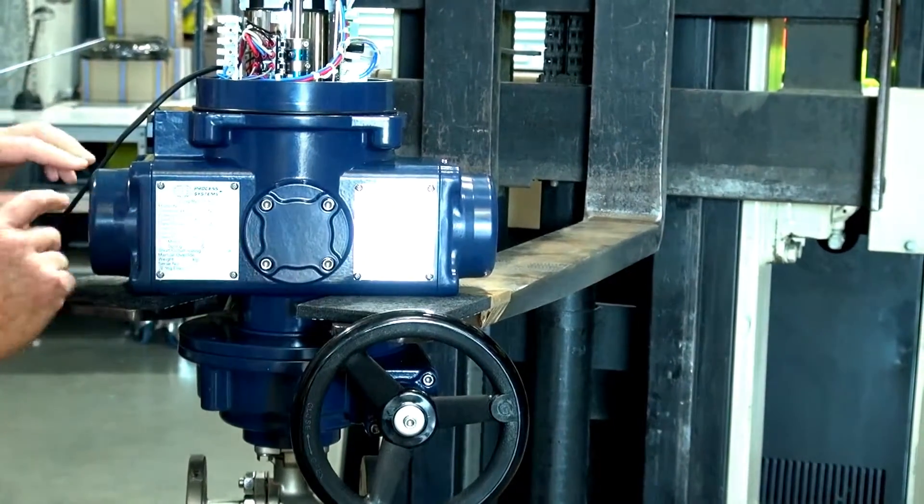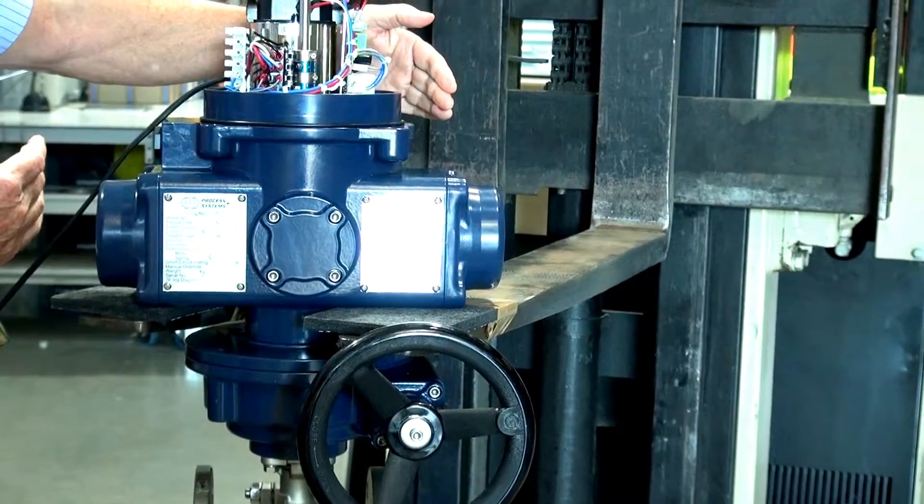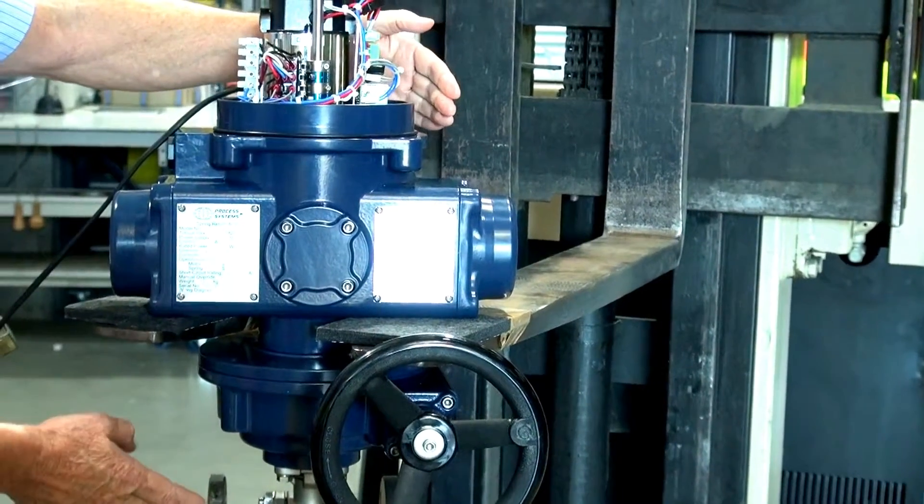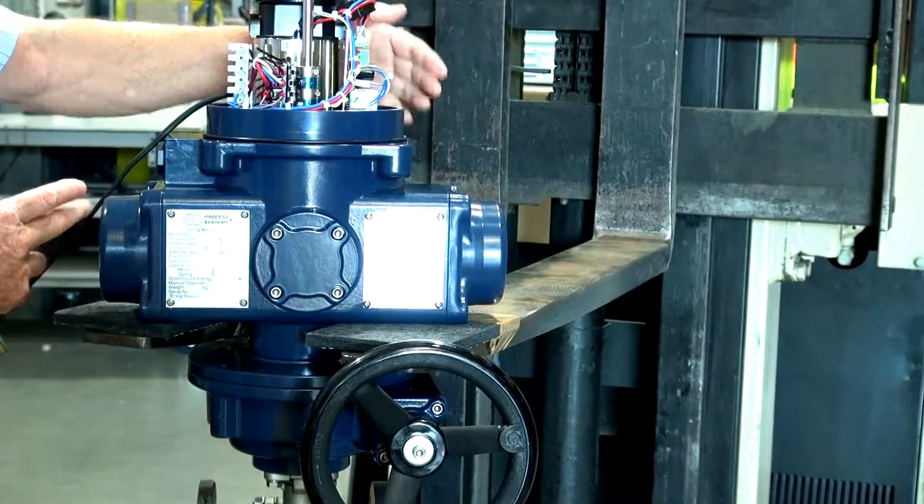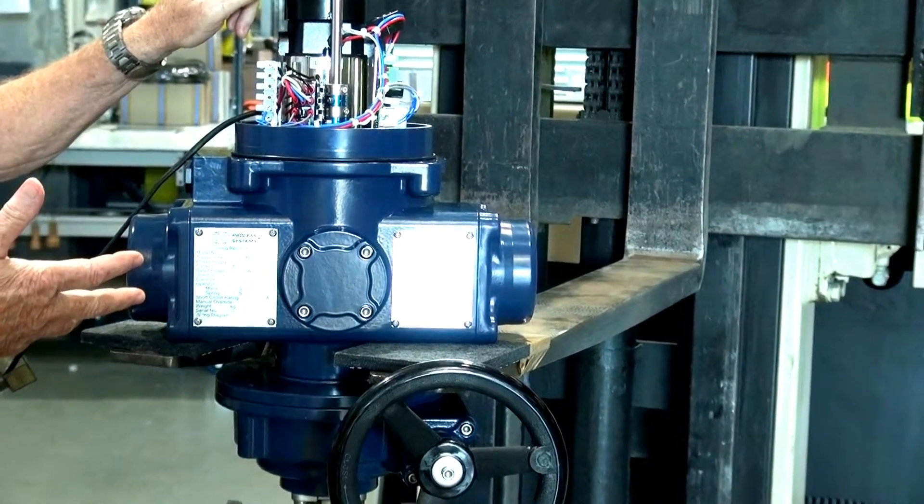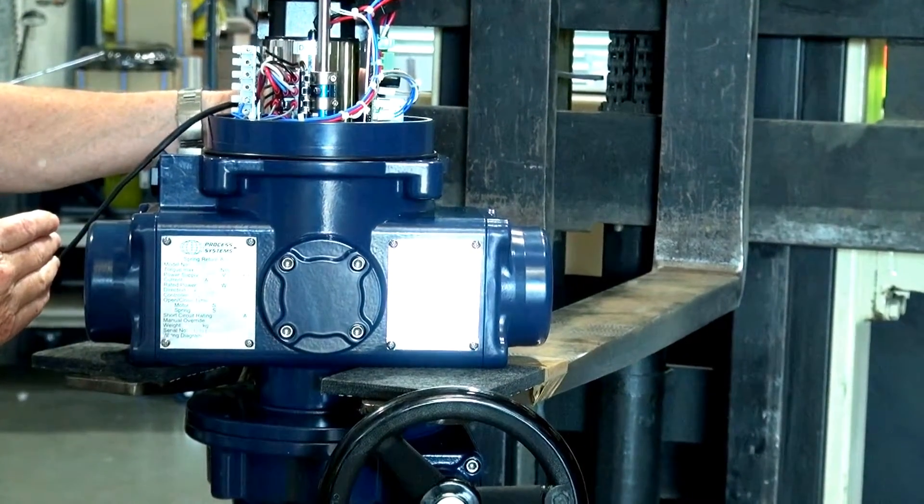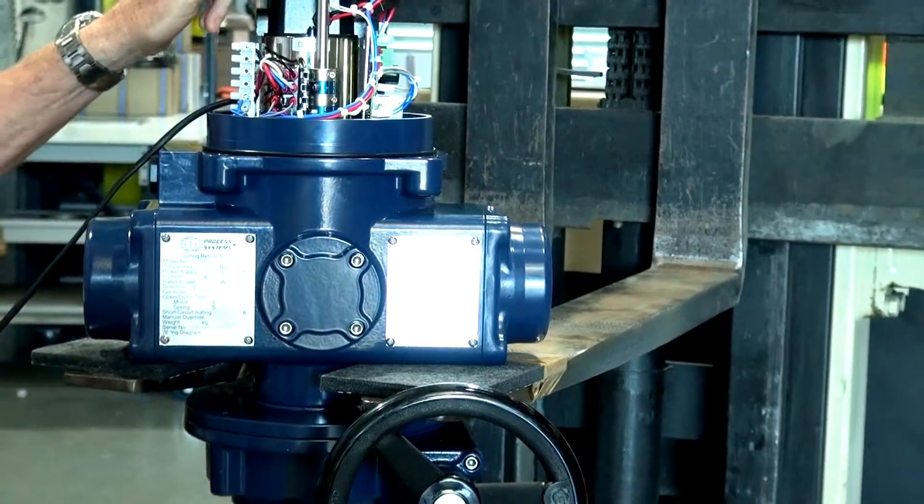A set of springs are mounted either side here. When the actual unit is open or closed, depending on which way the ball valve is set up, the brake here locks the unit off and it waits until such time when the power is removed. The springs then close the unit back down again.